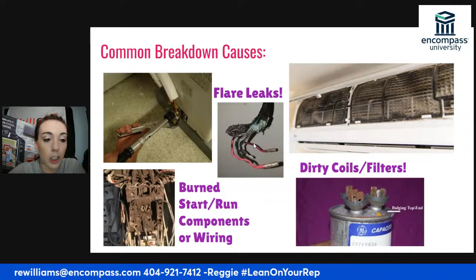If you are doing a maintenance, we think about the contactor, we think about the capacitor, we think about the dirty coils, we think about the flare connections. If you're there for a maintenance, you need to be checking every wire for connectivity. So if you open up the electrical panel and everything looks fine, nothing's melted, nothing's burnt, you still need to be taking each wire and doing the tug test, making sure that they're 100% connected and tight, making sure they're not going to bounce off of their location and arc throughout your electrical, because it would really suck if you were hired for maintenance and the next day something happened where that wire came undone and bounced around, arcing all of the start run components and the compressor.